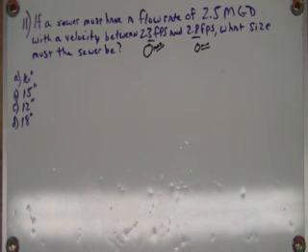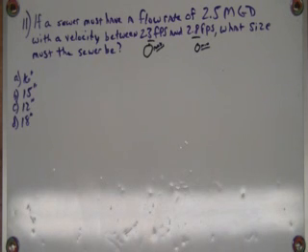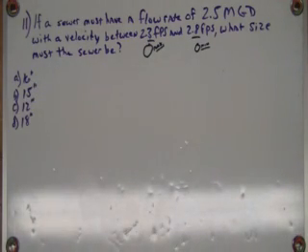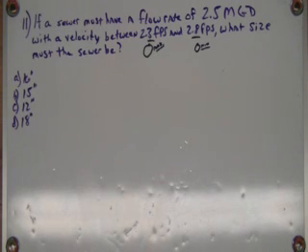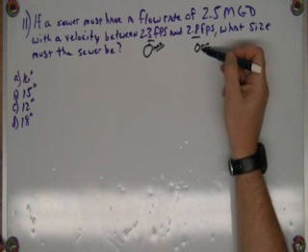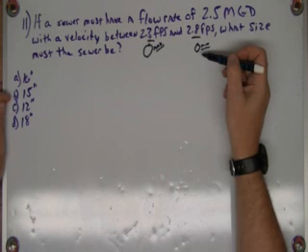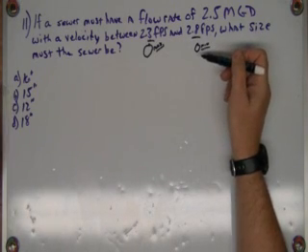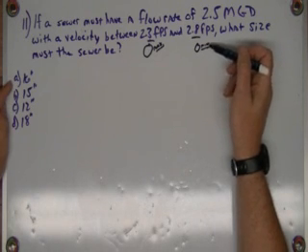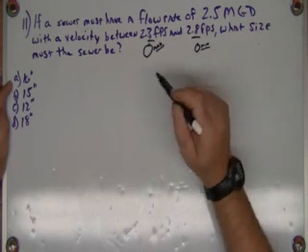I'm going to pick the pipe size based on the minimum velocity first and see where we're at. With these questions, the answer choices are designed to catch common mistakes — notice there's both a 15-inch and 16-inch option right next to each other. I expect we'll get about 15.5 inches for the minimum, so if it's anything more than 15 — even 15.00001 — you have to go to the next size up, which is 16.